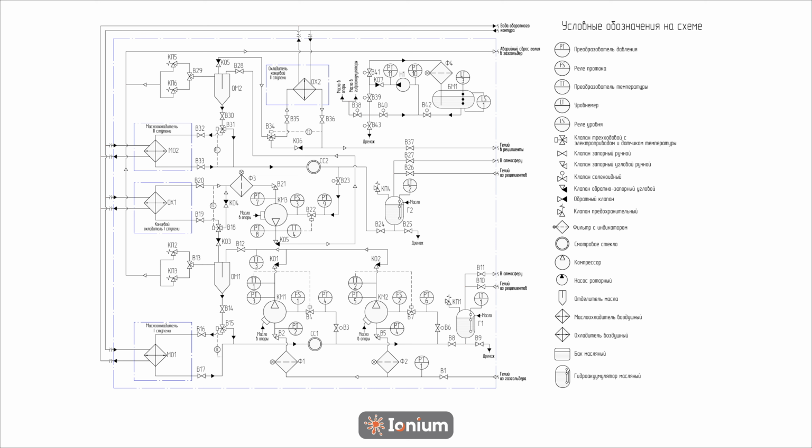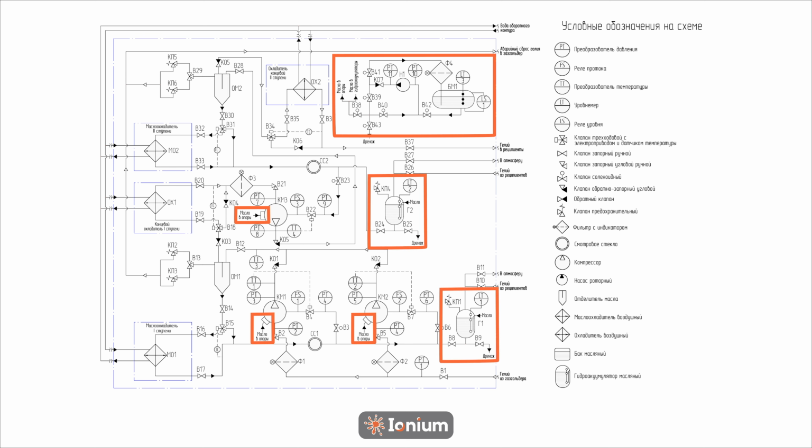In the compression block, it includes a circuit with an oil tank, BM1, featuring forced oil circulation, using a rotary pump, position N1, with an electric drive for cooling and lubricating bearings. It also supplies oil to hydraulic accumulators G1 and G2. The oil tank setup, BM1, enables cleaning of oil from mechanical particles by circulating it through filter F4.